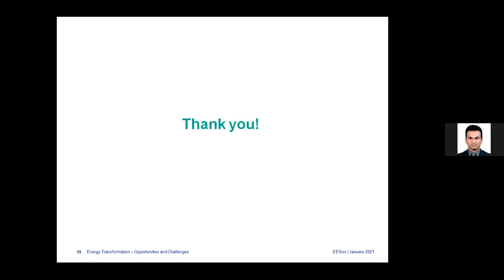Yeah. Other than this demand response, are you practicing curtailment as well? Sometimes, yes, because sometimes we have to. So is it for the renewable or is it for any other? I noted under frequency load shedding in your slides. Yes, we have under frequency load shedding, but normally it starts only when the frequency drops below 49 hertz. So we can't shed load because, under the rules, there are a few contingencies where we can't shed load. Say for a single generator trip, we can't shed load. Shedding is for the load side, but for the generator side, we go for curtailments.